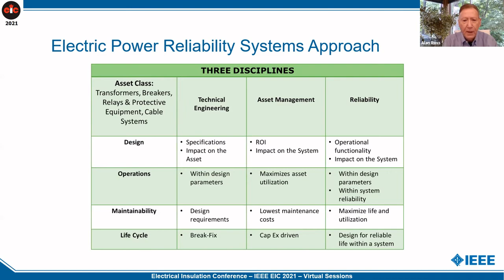So when you look at a high voltage system, these are the significant issues each of the different assets go through. All of them are obviously going through aging, but the poor maintenance of transformers, the oil gets dirty, it has water in it, and the more moisture you've got in a transformer, the quicker you're destroying the insulation. So moisture and insulation life are inversely related; the higher the moisture, the lower the life. What we found is in over 100,000 transformers tested a year by one of our organizations, through oil sample tests...